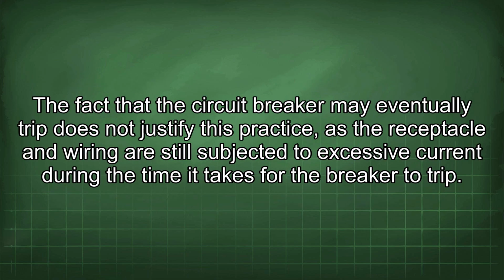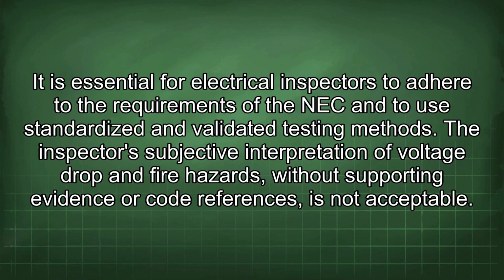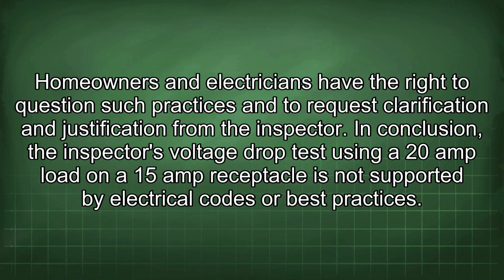The fact that the circuit breaker may eventually trip does not justify this practice, as the receptacle and wiring are still subjected to excessive current during the time it takes for the breaker to trip. It is essential for electrical inspectors to adhere to the requirements of the NEC and to use standardized and validated testing methods. The inspector's subjective interpretation of voltage drop and fire hazards, without supporting evidence or code references, is not acceptable. Homeowners and electricians have the right to question such practices and to request clarification and justification from the inspector.